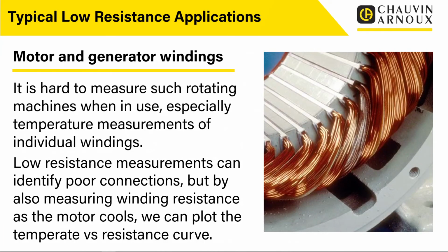So, motors and generator windings. It's hard to measure such rotating machines when in use, especially the temperature measurements of individual windings. You imagine, how do we measure the temperature of an individual winding within this motor while it's being used? Almost impossible. So low resistance measurements can identify poor connections. We can take the motor apart. We can go on the commutator or wherever at the end of the connections and check that we've got good connections. We might have a dodgy winding that's gone open circuit, or maybe even gone short circuit to a neighbouring winding. So we can check those as well.